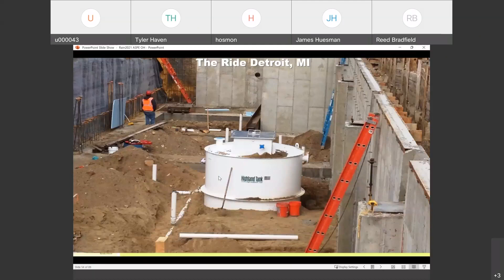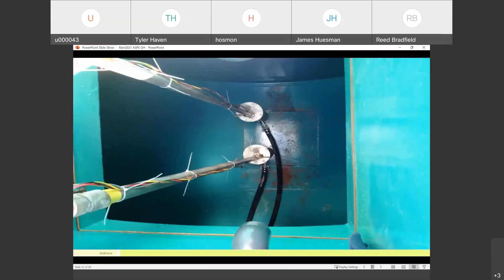Another application showing a partially buried tank — there's a water stop there, they'll pour the floor around that and then get to the top pumps. Pumps and pump controls — and again, access to the pumps can't be said enough. We don't want anybody going into a tank — it's confined space. It's like $4,500 per person to get an OSHA certificate to be able to go down in there. Even though it's just water, it's just not the safest thing in the world to be doing. Being able to have access to everything from grade is my number 1 thing whenever we're doing any design, regardless of whether it's concrete or fiberglass.